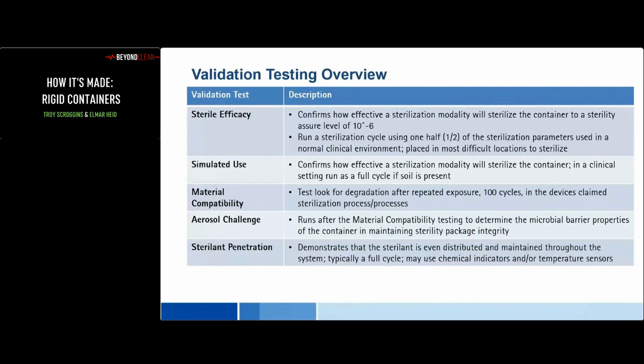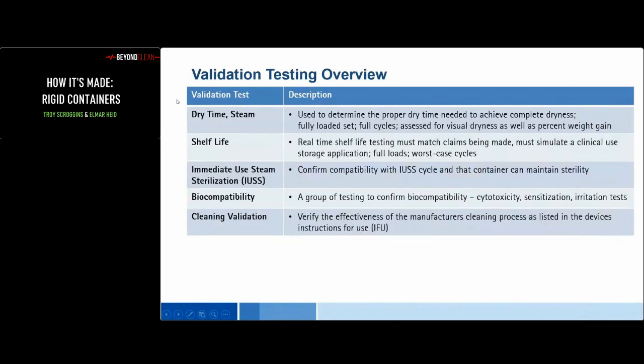Then another test is the sterile penetration. As you have different size containers and different configurations, it's very important to make sure that the sterilant can reach every corner of it. This test is meant to confirm, using either indicators or temperature sensors, that every section of the container does achieve sterilant penetration.